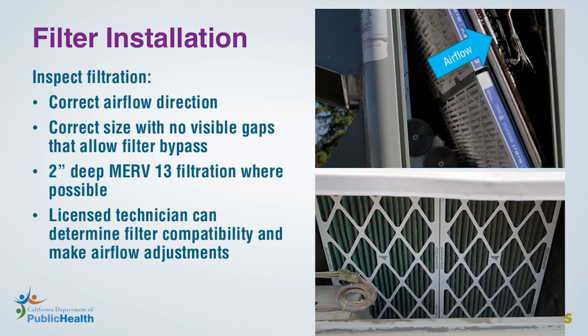Next, you'll want to inspect your filtration system. Ensure that the filters are installed facing the correct direction. There are arrows printed on the filters that should align with the direction of the airflow. To check the airflow direction, note that the airflow should pass through the filter before the copper coil.